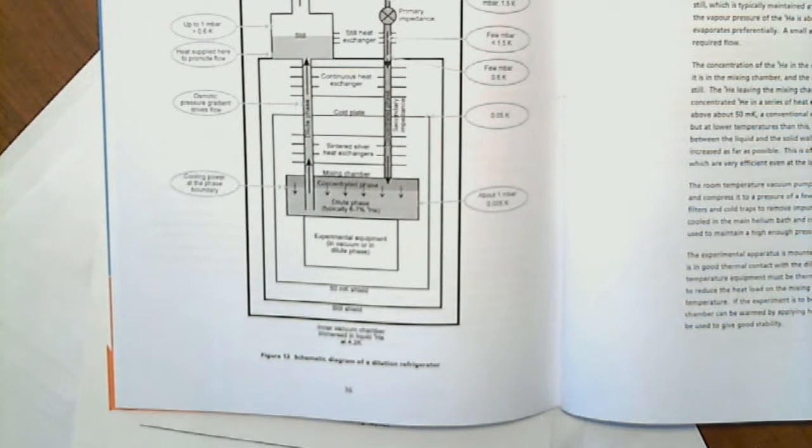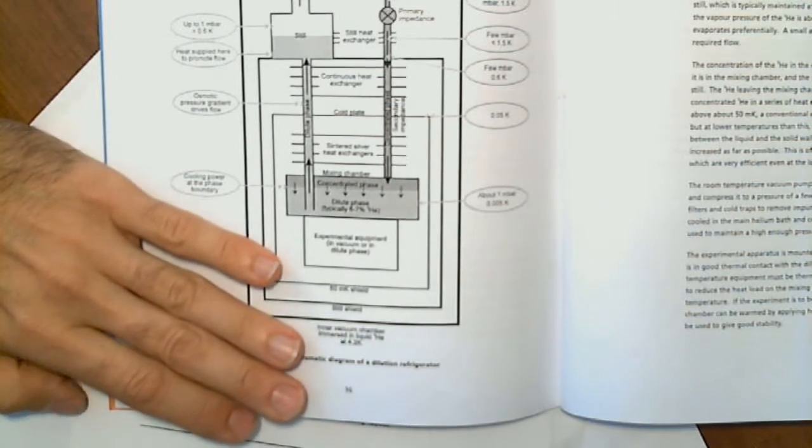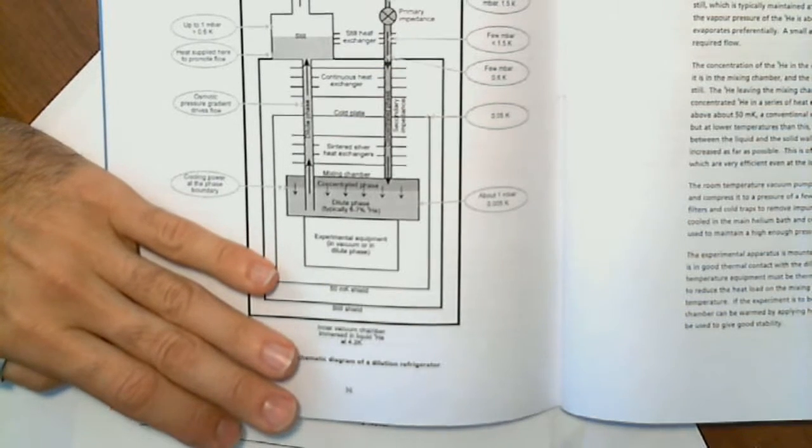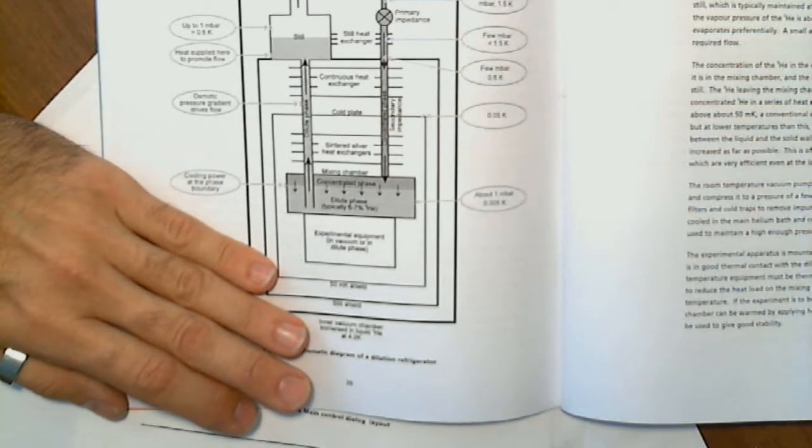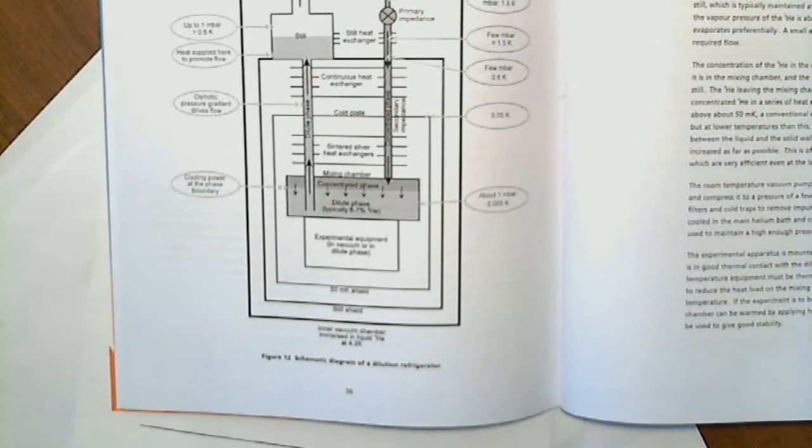Okay, and using this, you can cool down them from, let's say, 4 Kelvin down. Then we have this phase boundary, the helium-3 and helium-4 separate, and then you circulate, and the temperature comes down, down, down, and you achieve here 8 milliKelvin. Theoretically, you could go probably to 2 milliKelvin. The limits in the temperature, somebody asked yesterday, how much temperature you could come down. Depends, of course, from the outside, how many heat loads you have in the system as well.